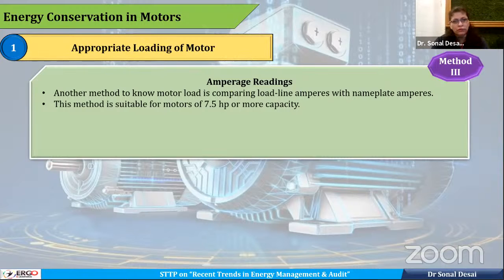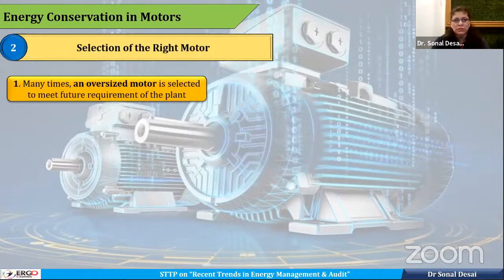So going for energy saving potential in motor, first and foremost is selection of the right motor. Just like pump, it is important that the motor should have a right choice made. Then only we will be making it operate at a right efficiency. Many times an oversized motor is selected to meet future requirement.